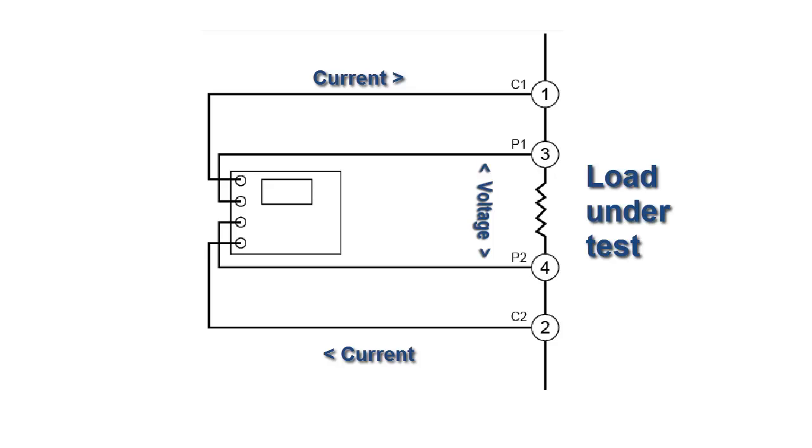There is virtually no current flowing through the sense probes. Nearly all the current flows through the source probes. This allows for a high level of measurement sensitivity and accuracy when the load under test is of low resistance.